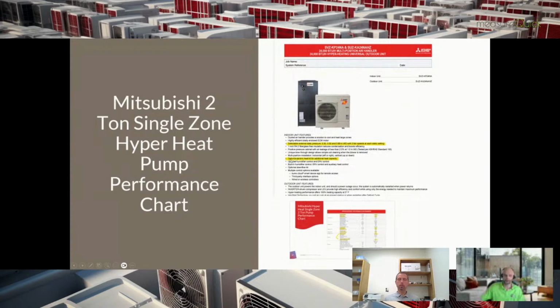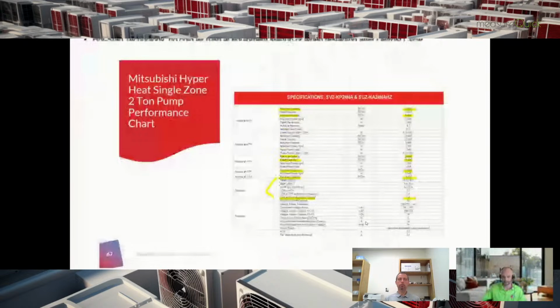And then you'll see here, this does have the capacity to put electric heat strips in if we needed to do that. There are some very cold climates where code requires you to put in resistance backup heat, or some kind of backup heat, no matter what. If you're installing a heat pump, it doesn't matter what you say or what the programs say, the local code does require you to do that. They require it because they get to extreme temperatures where these heat pumps, no matter what they are, just are not going to work right now. But you get a lot of benefit out of them. So let's look at a few things here.